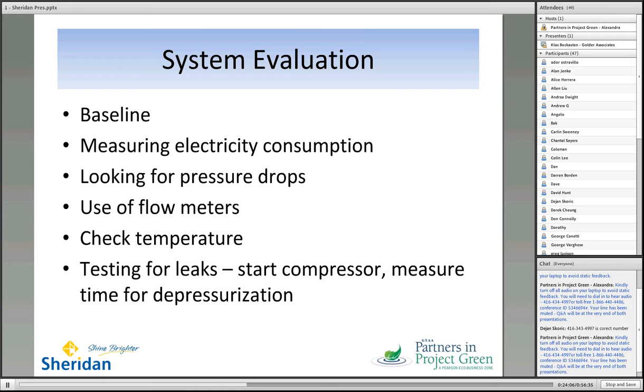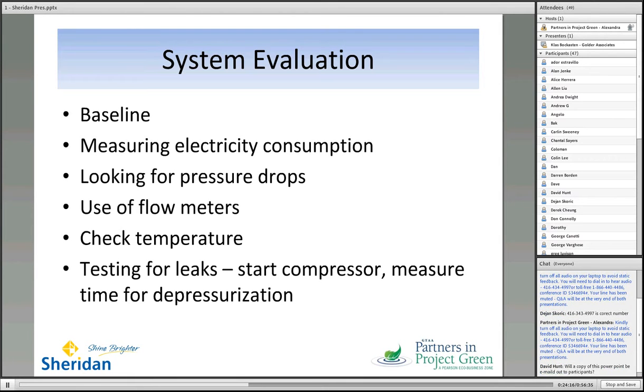Look at the operating temperature. Use some flow meters. All of these things give you a sense of what you would expect the system to do. And if you repeatedly come back and check, and you see a change in any of those values, it could indicate that somewhere along the way, you've got something to address.